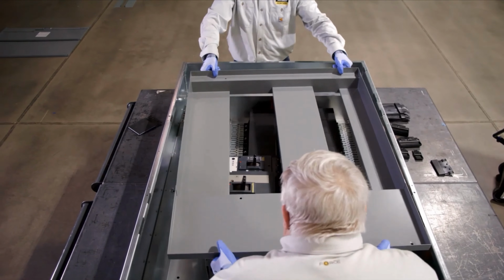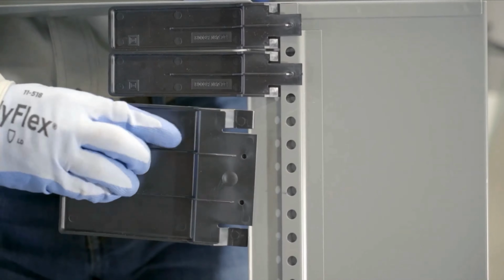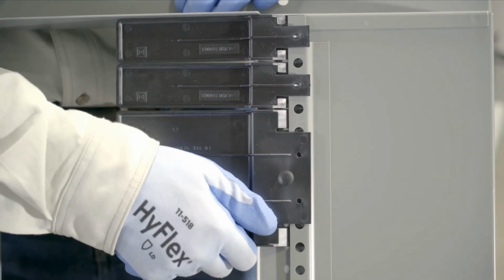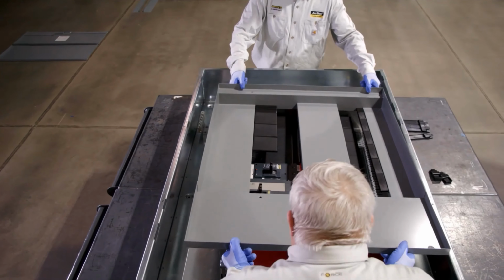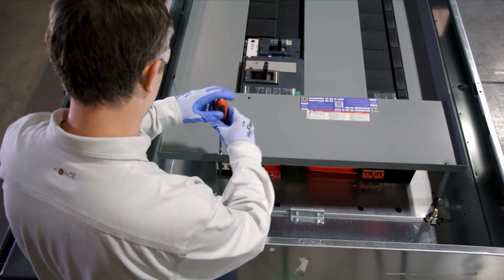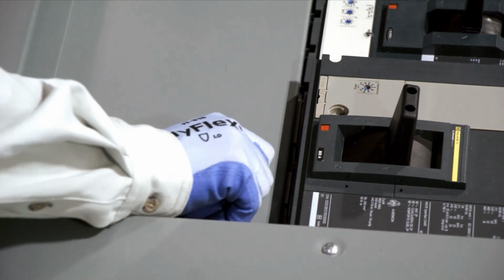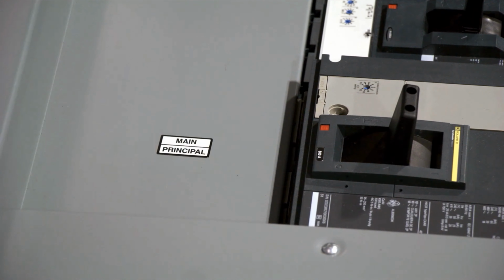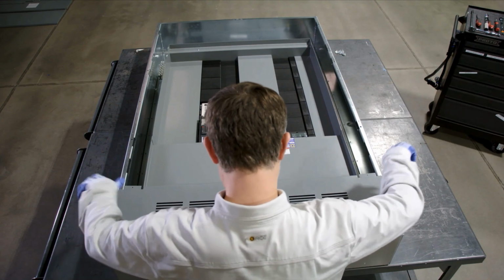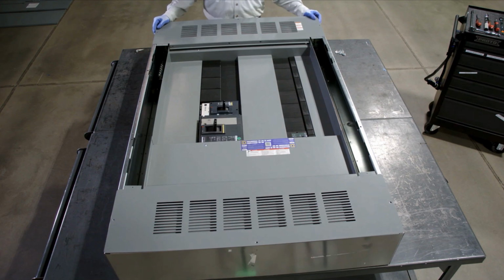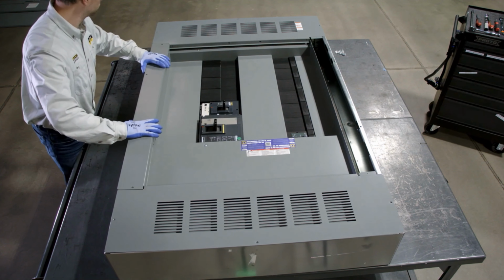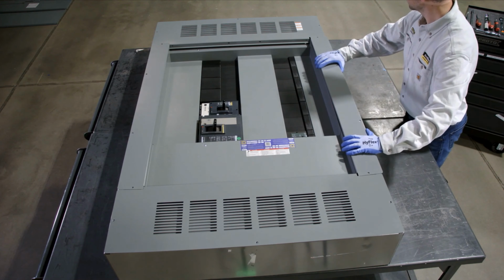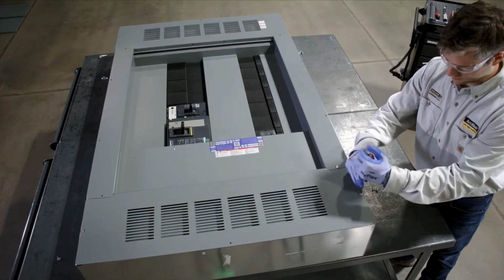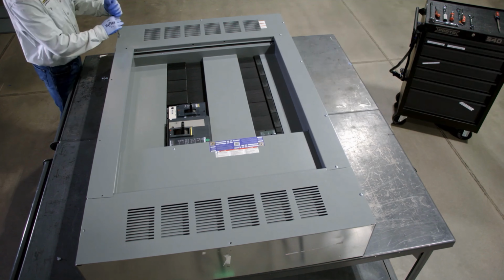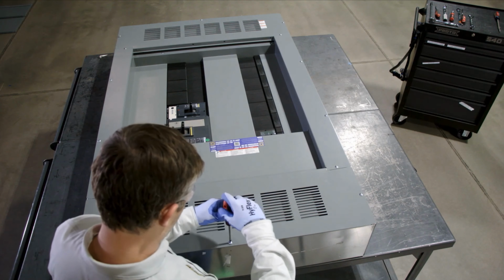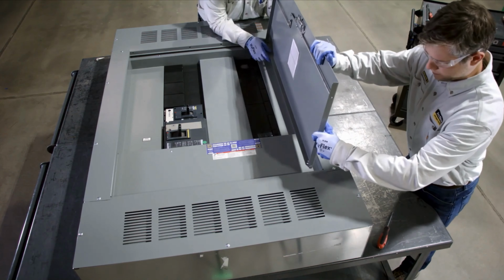Remove the interior dead front to install blank extensions. To install blank extensions, simply square the blank extensions to the interior dead front. Then, reinstall the dead front, securing it with the screws provided. For main circuit breakers only, attach the main circuit breaker label to the circuit breaker cover. Now, install the end trims. Install the side trims. Adjust the fit and tighten all the screws to complete the installation of the trim. Finally, fit and secure the door panels.